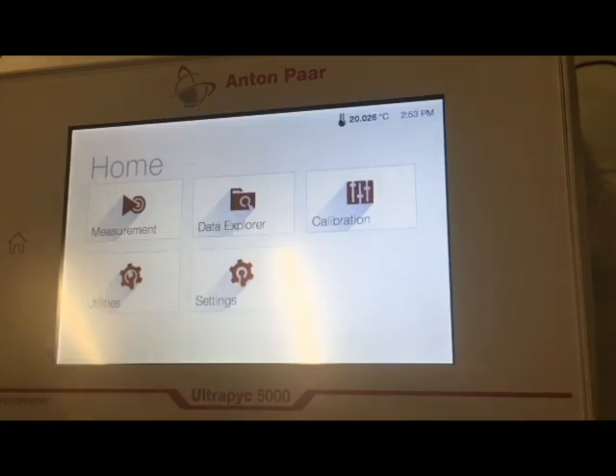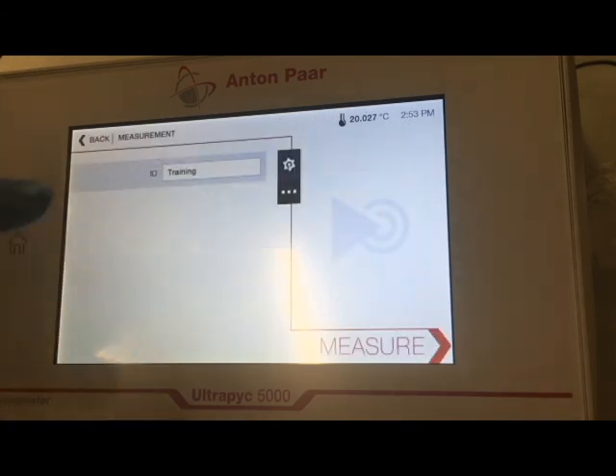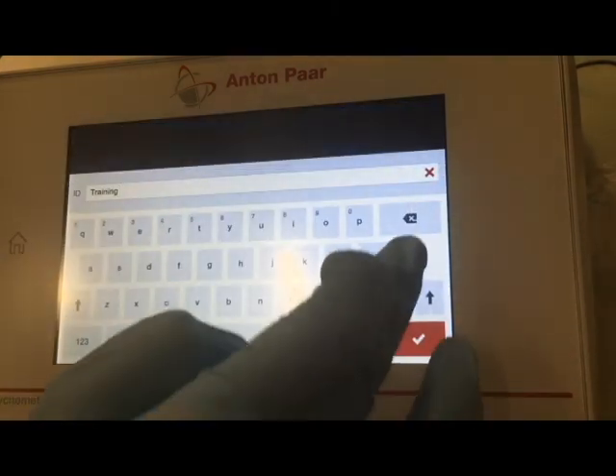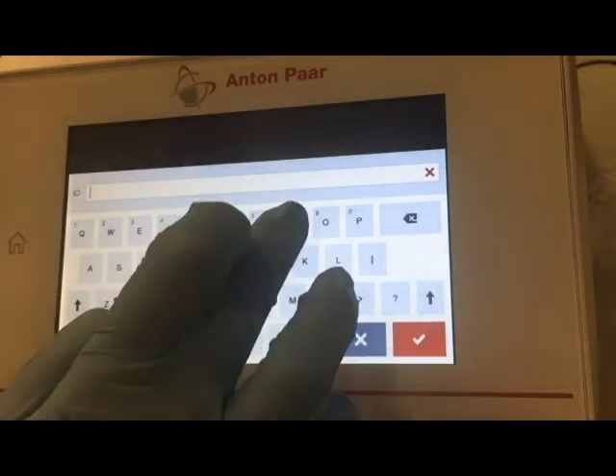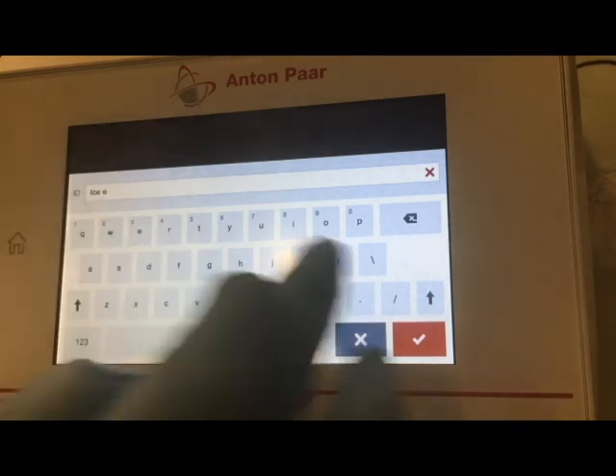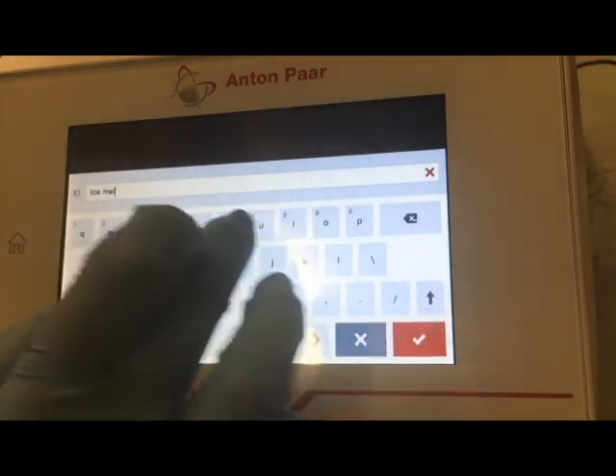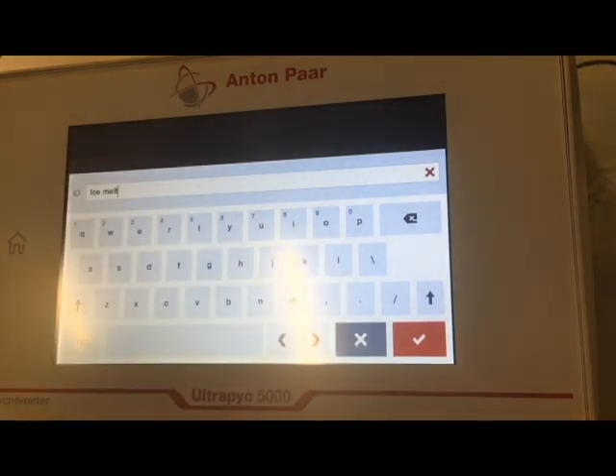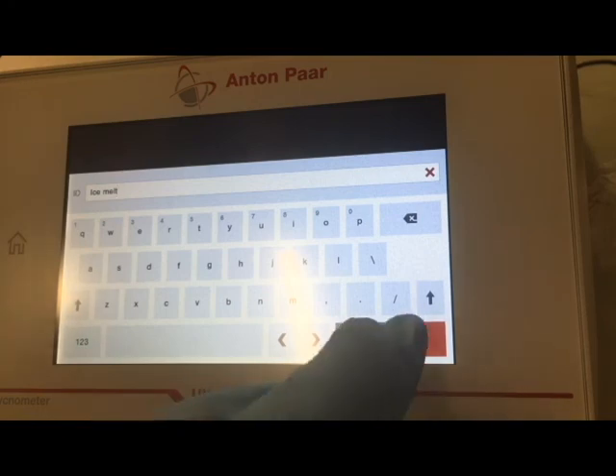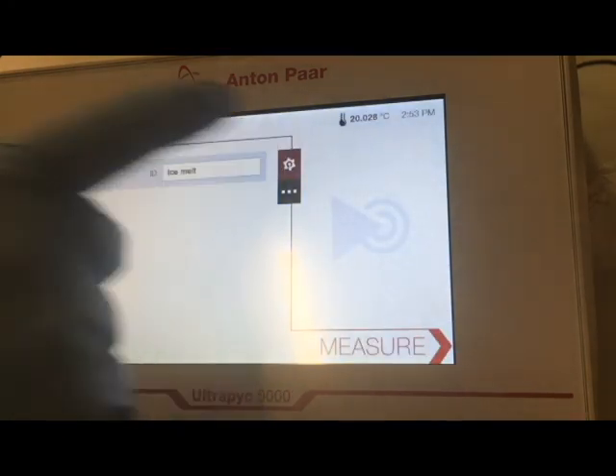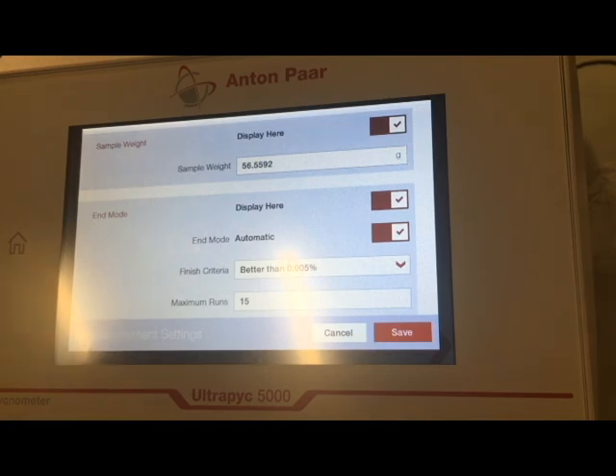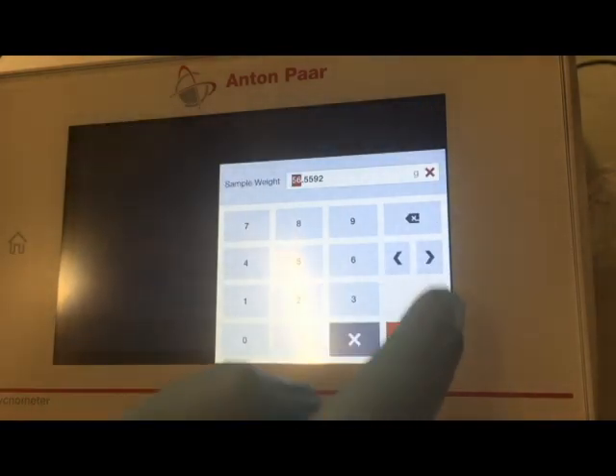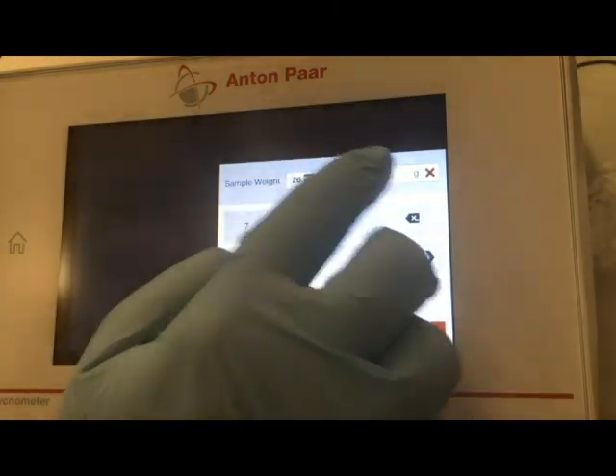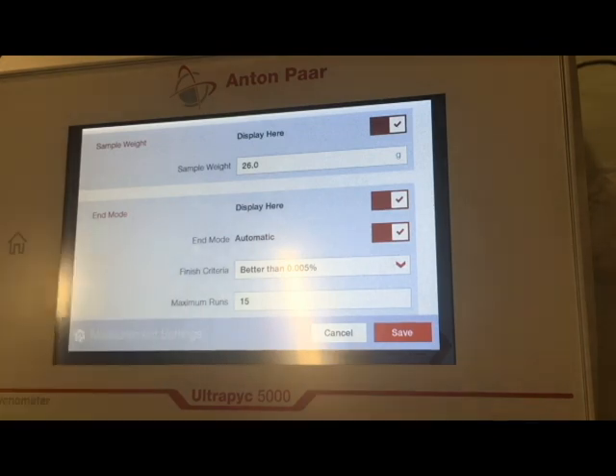Back at the screen on the instrument, I'm going to press the home button to make sure that I'm on the home page. And this time, once we've got a finished full calibration, we're going to go to measurement here. I'm going to type in the name of my sample here, which will be ice melt. It's a good idea to put a date with the name of your sample, especially if you're going to be running samples that are similar to one another. And I'm going to press this little gear icon here to go into the settings of this ice melt run. So I'm going to type in my sample weight in grams, and I have 26 exactly. I measured out exactly 26 grams.